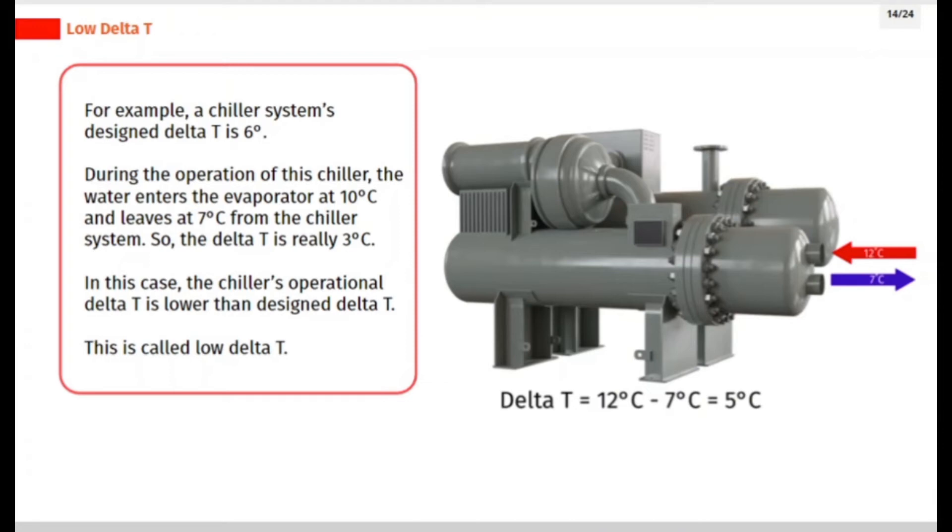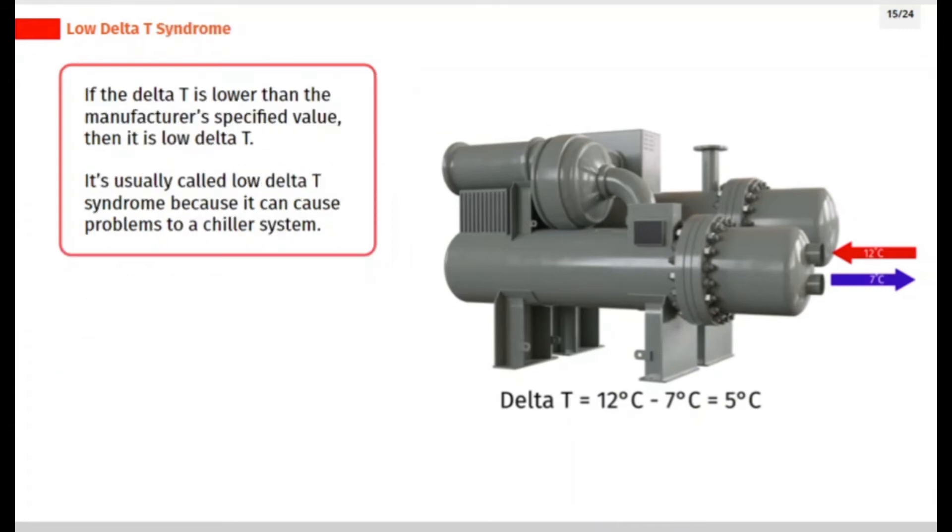In this case, the chiller's operational delta T is lower than design delta T. This is called low delta T. If the delta T is lower than the manufacturer's specified value, then it is low delta T. It's usually called low delta T syndrome because it can cause problems to a chiller system.